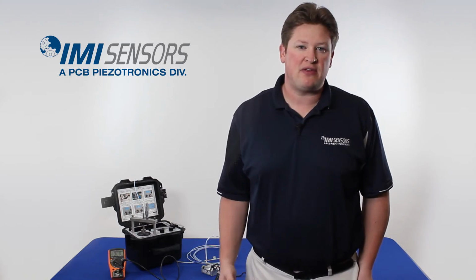Proximity probe calibration is one of the most common questions we get. And there are actually two methods of proximity probe calibration. There's static and dynamic proximity probe calibration. A static proximity probe calibration is where the technician measures the DC voltage output from the proximeter at known gaps from the target, 10 mils, 20 mils, 30 mils, and so on, and plots those results on a curve.